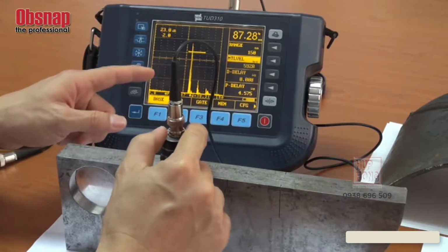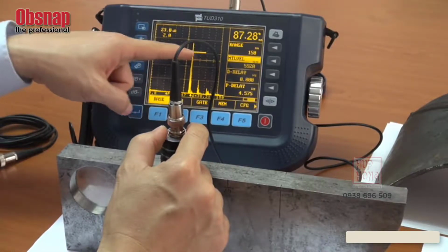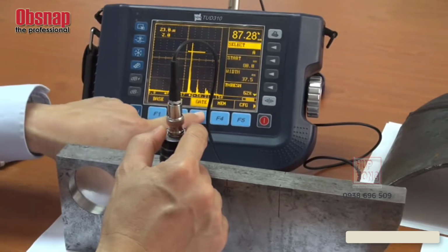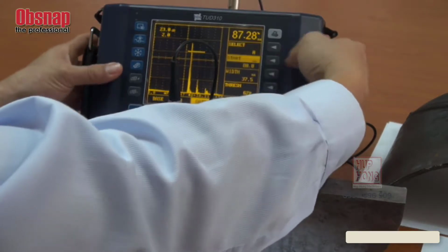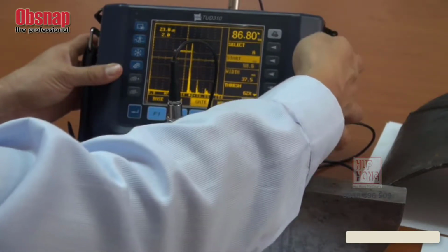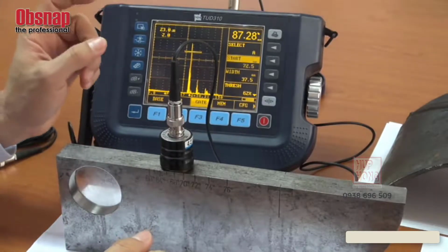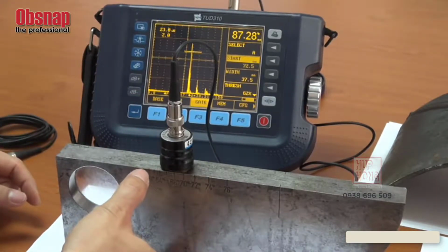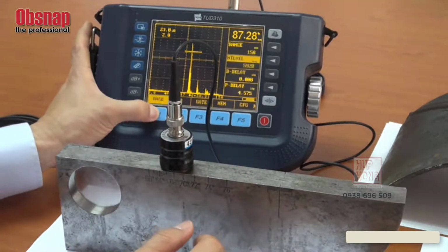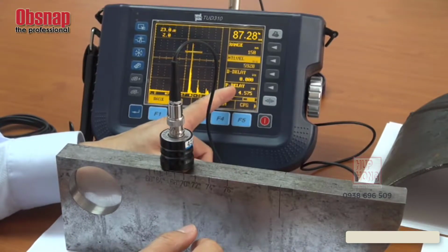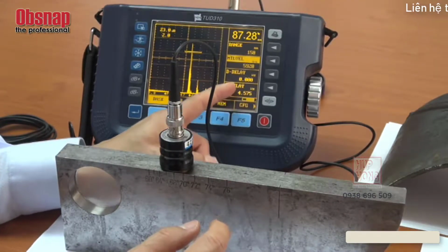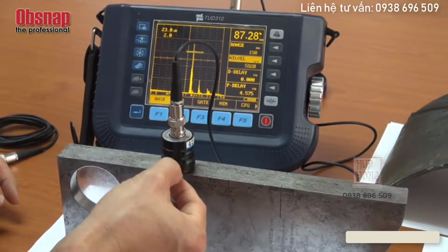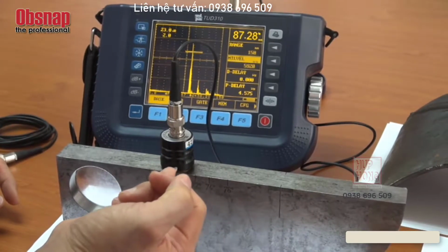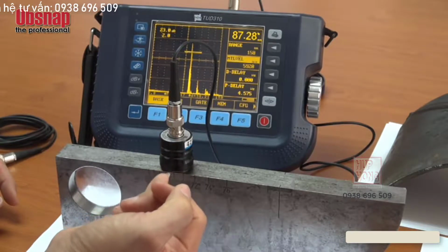Now, what is this? This thing we call the gate. It's actually for measurement purposes. I need to press this so that by moving it, I set the start position. When I stop here, it's taking the reading here. But is it accurate now? No, it is not. It's supposed to be 100 mm. Am I right? Yes. What else do we need to adjust? Let's go back to the page. It is this probe delay. Probe delay is one of the functions that we use to compensate for the delay of the sound wave that comes out from the crystal of this probe to the material.